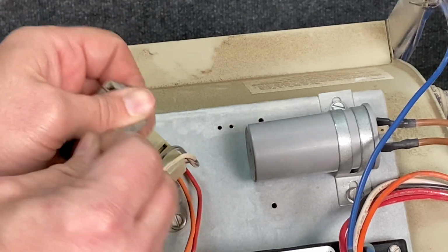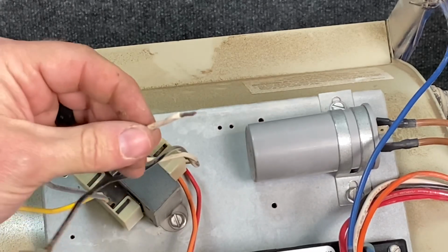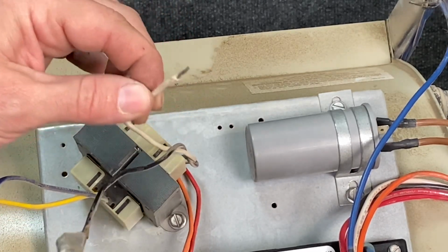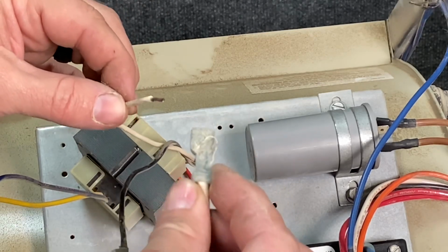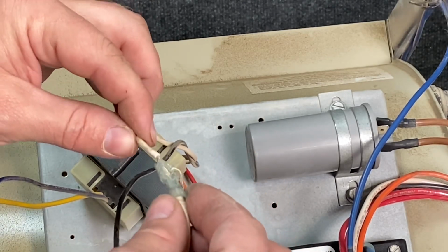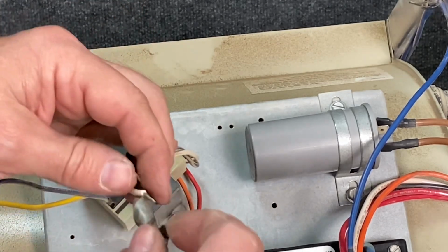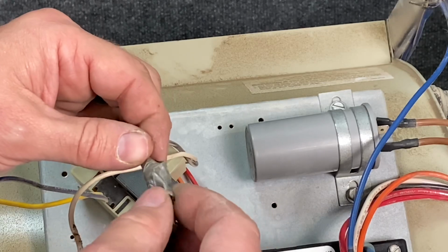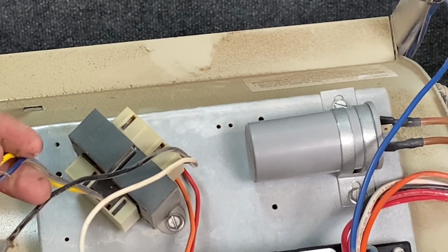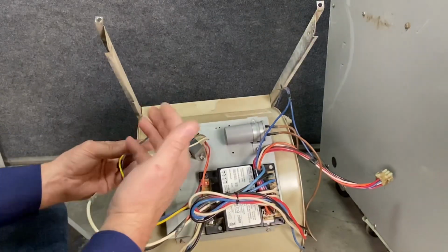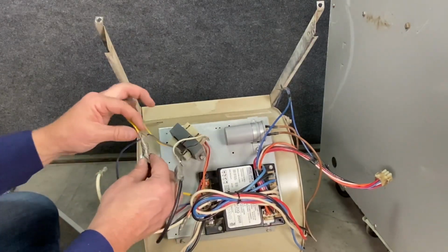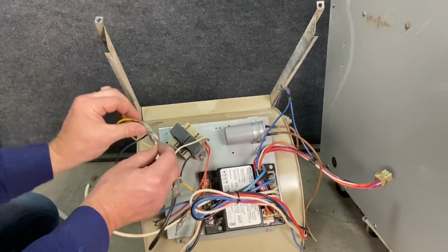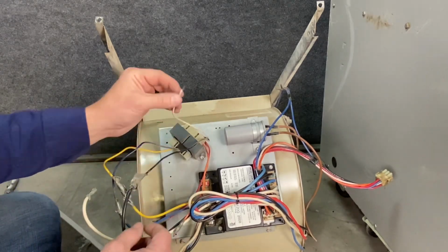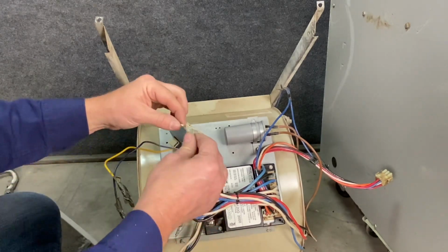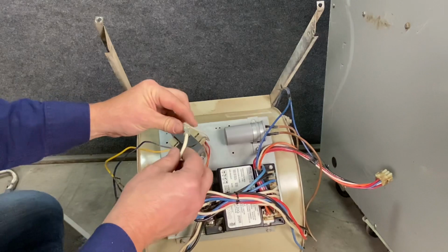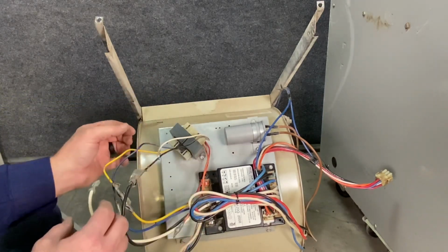And oh my gosh, this is scary. All they did is take the raw wire from the new transformer. They left the plug that was on the old transformer, and they just shoved it inside and taped it up. That is absolutely horrific. You can see how brittle this tape is. It's really surprising that the tape hadn't caught on fire. And they should have put a fuse in. Anytime that you change out a transformer, you always add a fuse on the low voltage side. So where the yellow wire was here, I would have put a fuse in line there. Another thing I would have done is put a male terminal here, so that the female terminal would have slipped into the same exact wiring harness. It doesn't take that much extra work to put the system back like it should be.